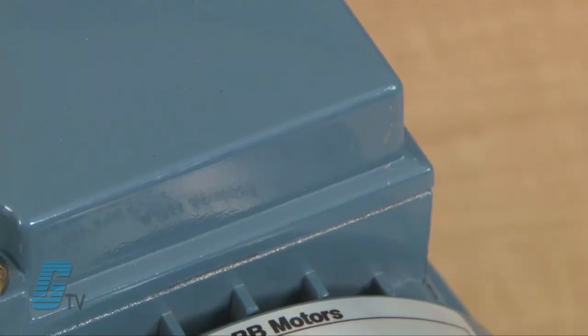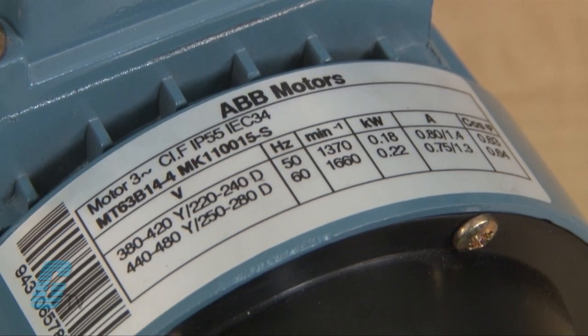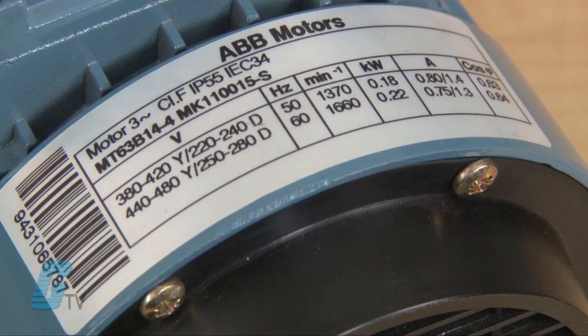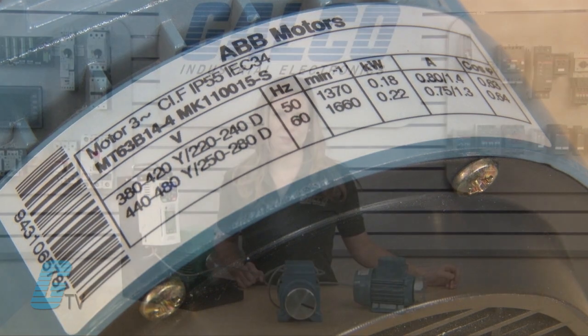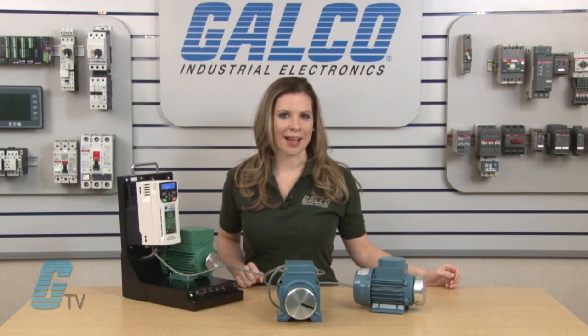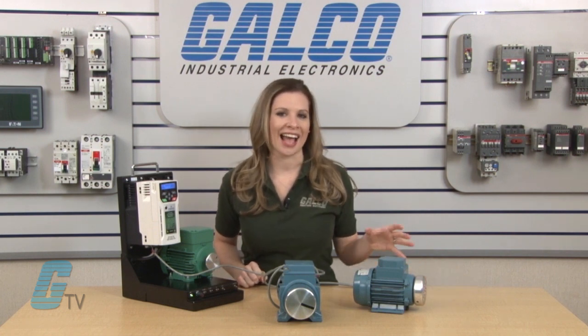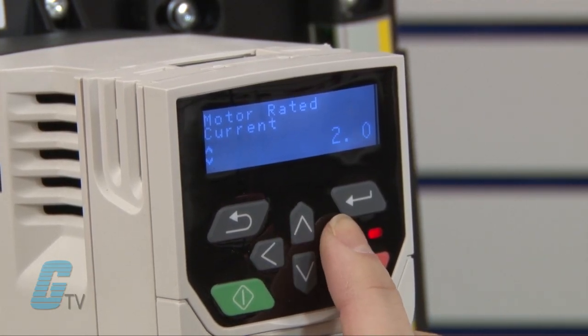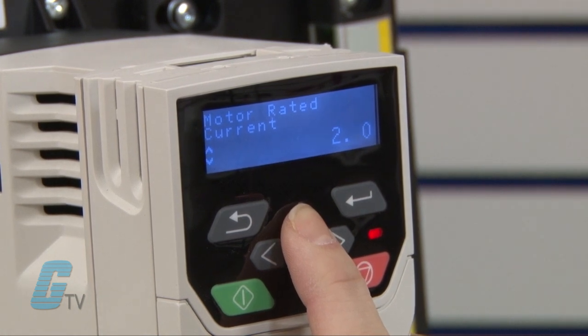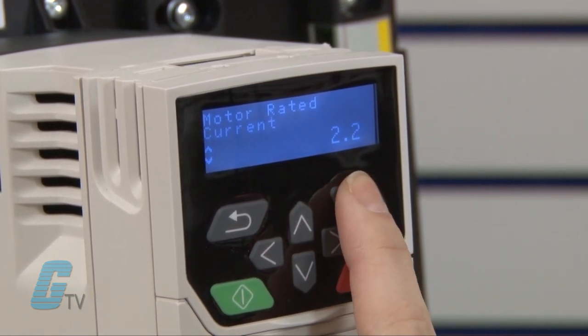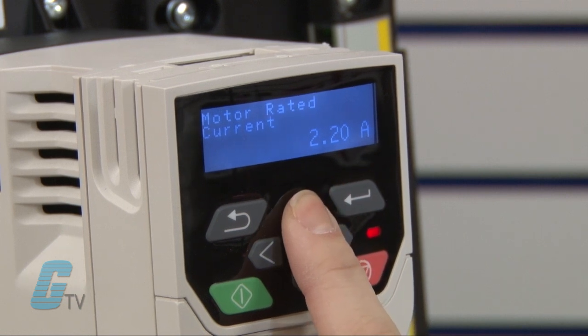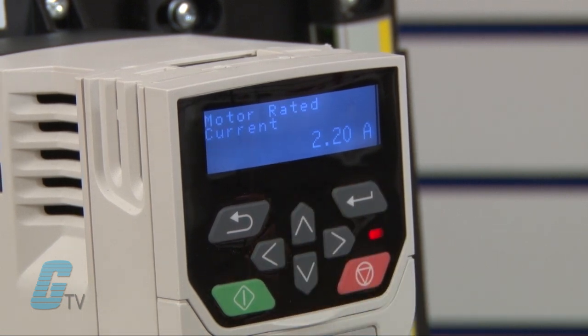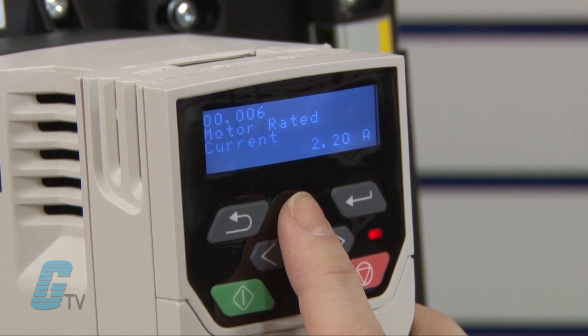I will show the first scenario with multiple motors. I will need the motor nameplate data for each motor and record the amount of current for each one. Then I will find the average nominal speed by adding up the speeds of all the motors and dividing by the number of motors. When entering the nameplate data for the drive, I can enter the accumulated current, assuming it does not exceed the drive's rating. I will also enter the nominal speed as the average.